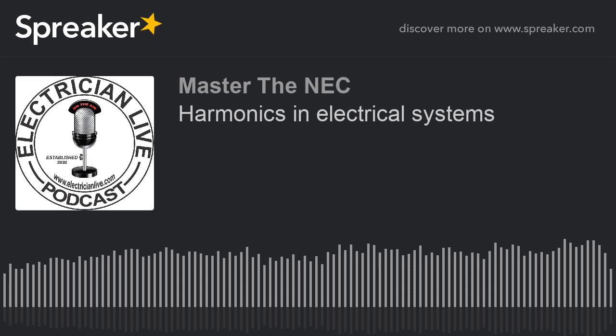Some of these generators are very sophisticated, and whether they create what's called a dirty signal or not, or how they function, and the switching components between the standby and emergency can be affected by these harmonics. So you need to be aware of that. Also, any type of data processing equipment can be extremely sensitive to harmonics.